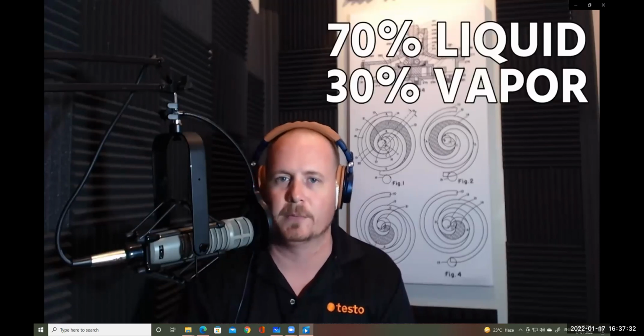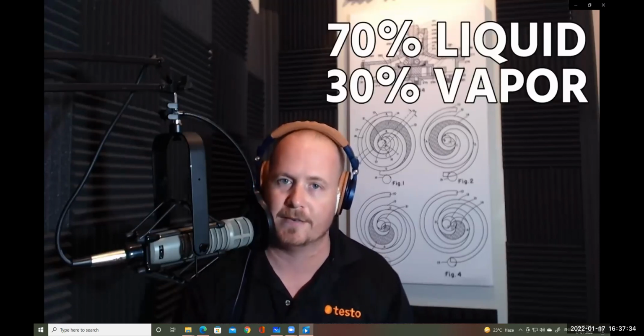Right when it comes out of that metering device, it has already flashed off some of that refrigerant from liquid to vapor. A lot of books will say approximately 70 to 30%. So 70% would be liquid, 30% would be vapor when it enters that evaporator coil, but that varies quite a bit, and there are a lot of conditions that impact that. But right as it enters the evaporator coil, it's automatically changing state and it's boiling.